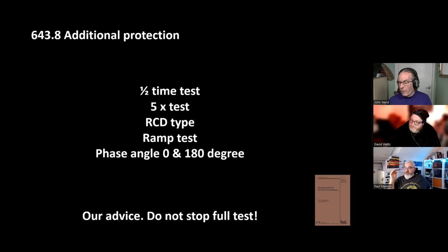This nonsense. Test at terminals without load connected, fine. But do it again with load connected. Remember something: with RCD testing, you are verifying the performance of your installation with connected load. Sometimes you can't do that. But this is the problem, I think, Paul. If you say to yourself, I am doing the manufacturer's product testing and confirming the 1 times I delta N, then fine. If you say, I've selected this device for the requirement of additional protection with regards to the utilization I've observed and the equipment that's been selected, and then you select an A type and all this stuff, then you go to the device and test I delta N AC, you're not going to verify any of that safety that you've really selected for.